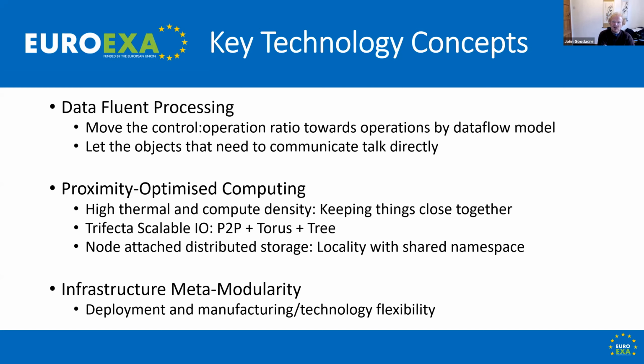That then drove other problems. As soon as you say everything's got to be close, what you're actually doing is bringing the thermal and compute density significantly higher. And this is where a section of this talk will look at what we did in the infrastructure to be able to support a 5+ times increase in thermal density associated with what you can do with compute, all around keeping those wires short, keeping things close, keeping things local.